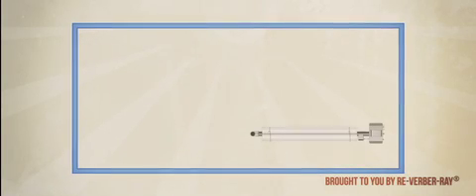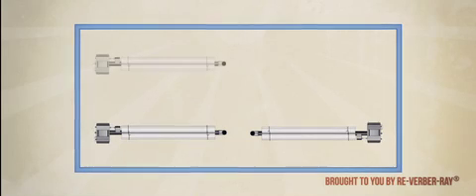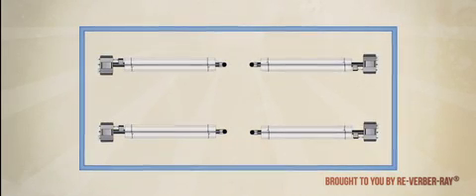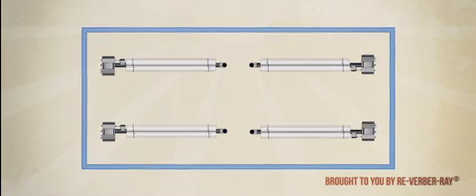As a rule, multiple heaters of lower BTUs are preferred over single, large BTU models. However, heater selection is generally based on the available mounting heights and clearances where the heater will be located.